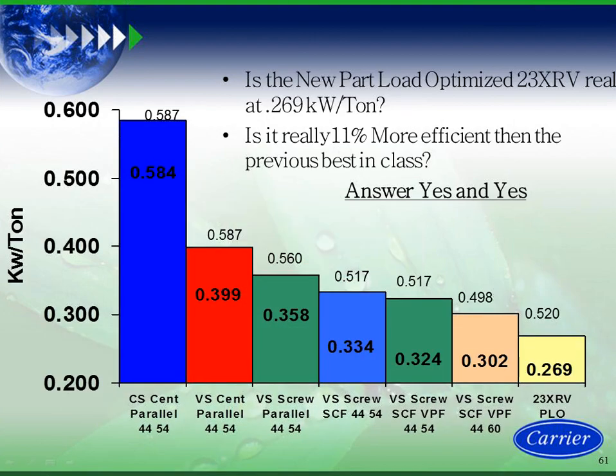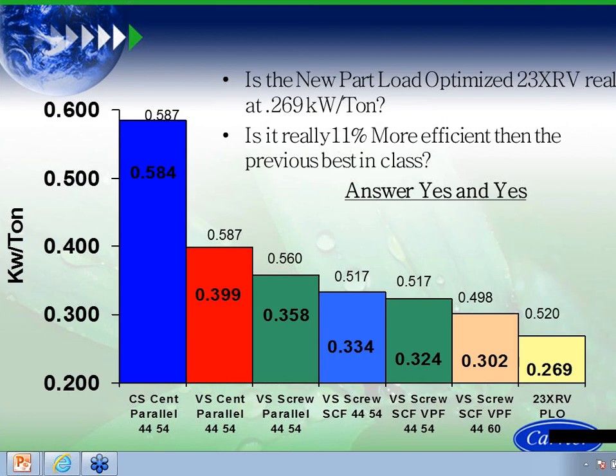So now let's look at where we're at now. With the part load optimized machine, we are able to achieve 0.269 part load efficiency. Again, the full load went up, okay, 0.520. But how often do we operate a building at design day when the building's fully occupied? It almost never happens, right? So we're 11% better than the previous best-in-class 23XRV running at a 0.302. So we're running at a 0.269 from a chiller plant standpoint at 800 tons. No one else can touch this in the industry.